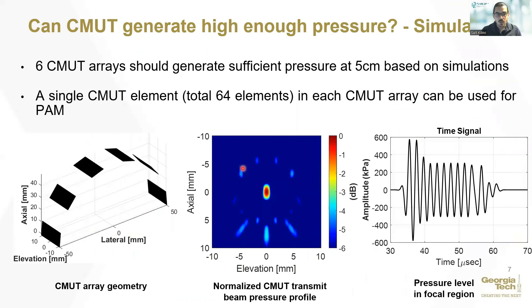The next question we are trying to answer in this study is if we can replace piezoelectric transducers with CMUT. We have previously shown that we can obtain around 100 kilopascal negative peak pressure with a single CMUT array. To achieve sufficient high pressure levels with multiple CMUT arrays for therapeutic excitation, we performed sets of acoustic simulations. The design of six CMUT arrays is shown in the bottom figure left. That design has a 50 millimeter focal distance. The attained pressure profile is shown in the figure middle, and it is demonstrated that we can obtain over 300 kilopascal peak negative pressure with an orientation of six CMUT arrays.